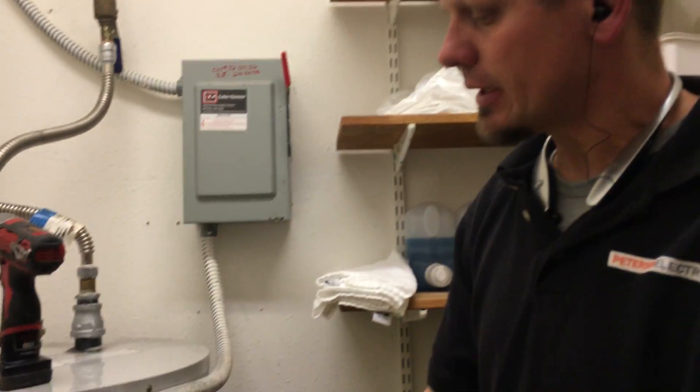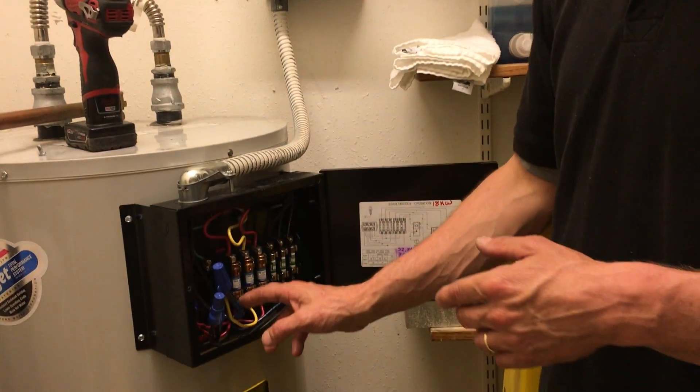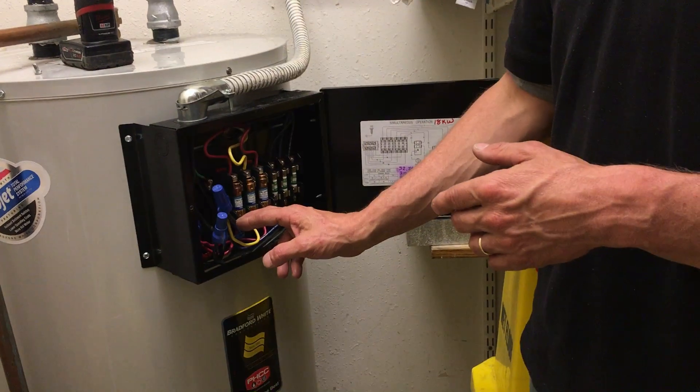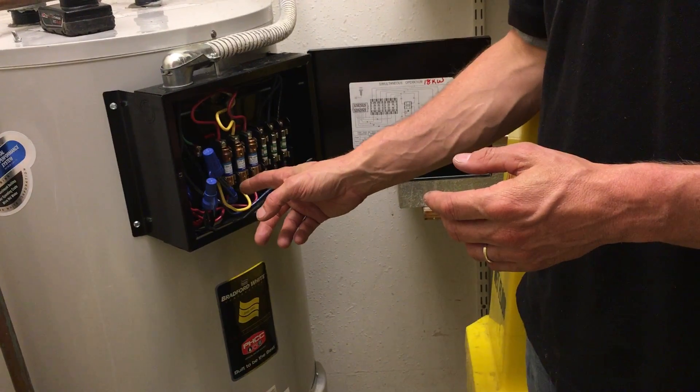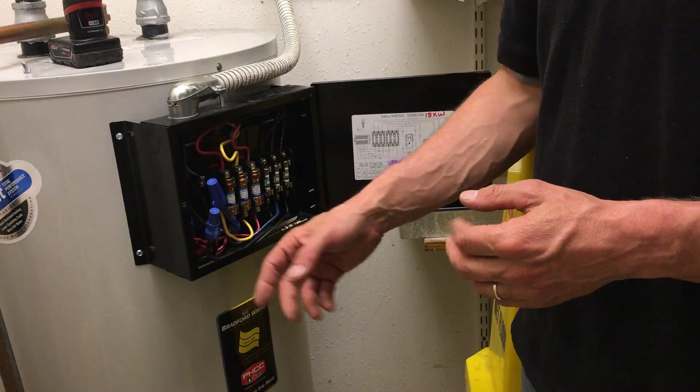Personally, this 6-gauge is going to do just fine if I'm truly drawing 37 amps. This THWN-2 is good up to 60 amps in the 310-15B column. So if you guys look that up in Article 310, the 2017 code.